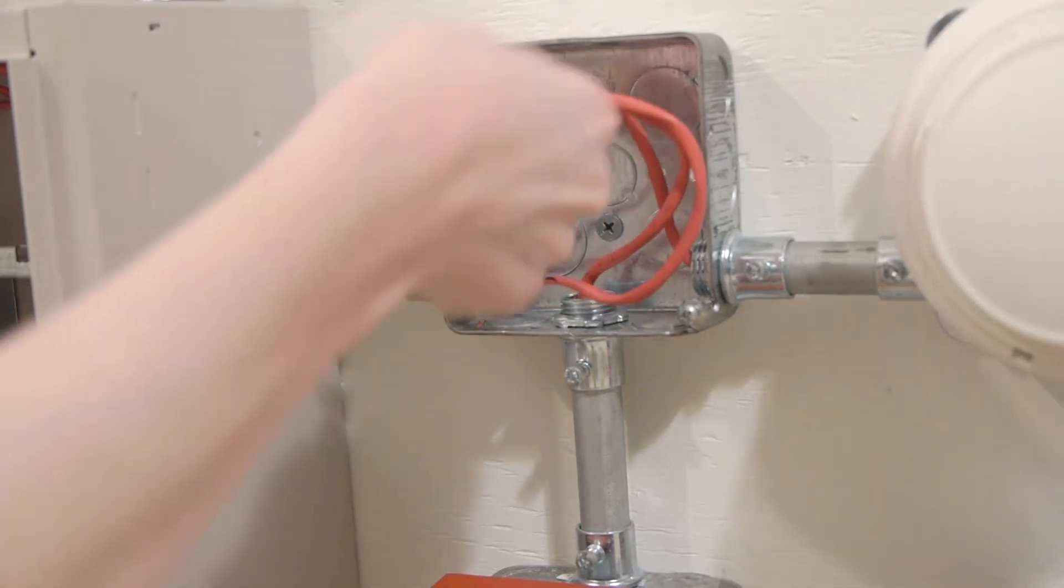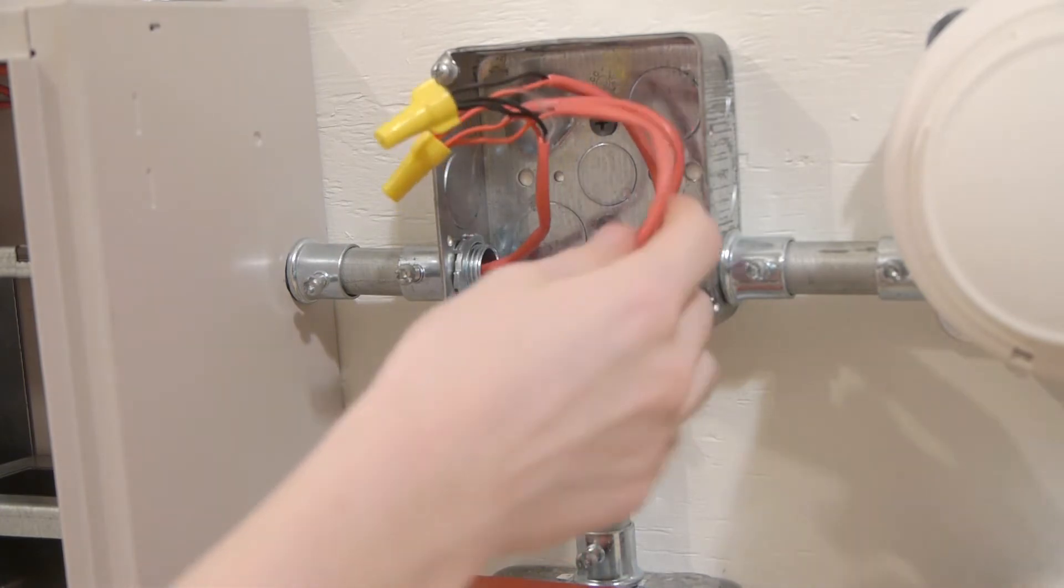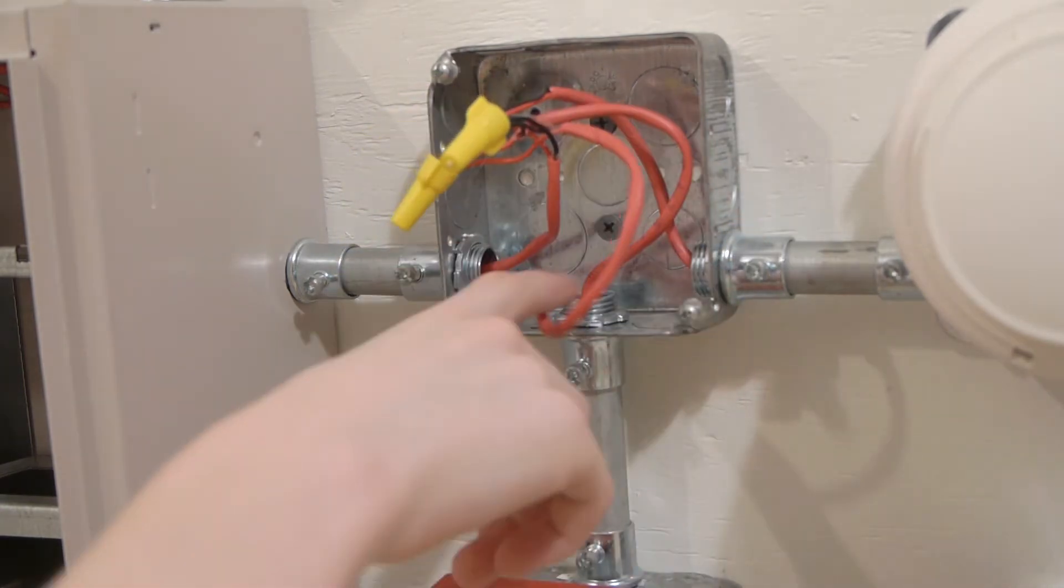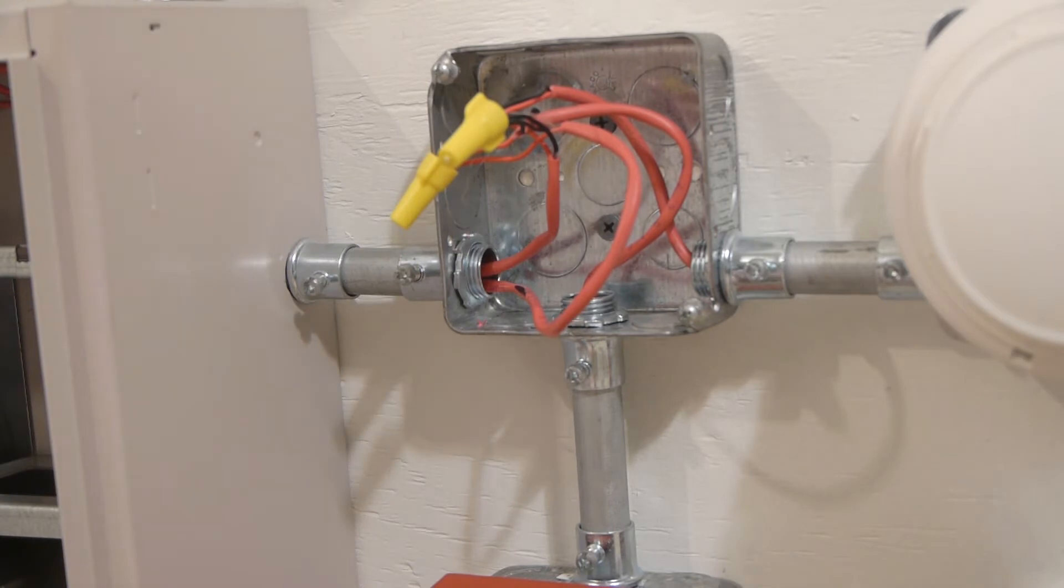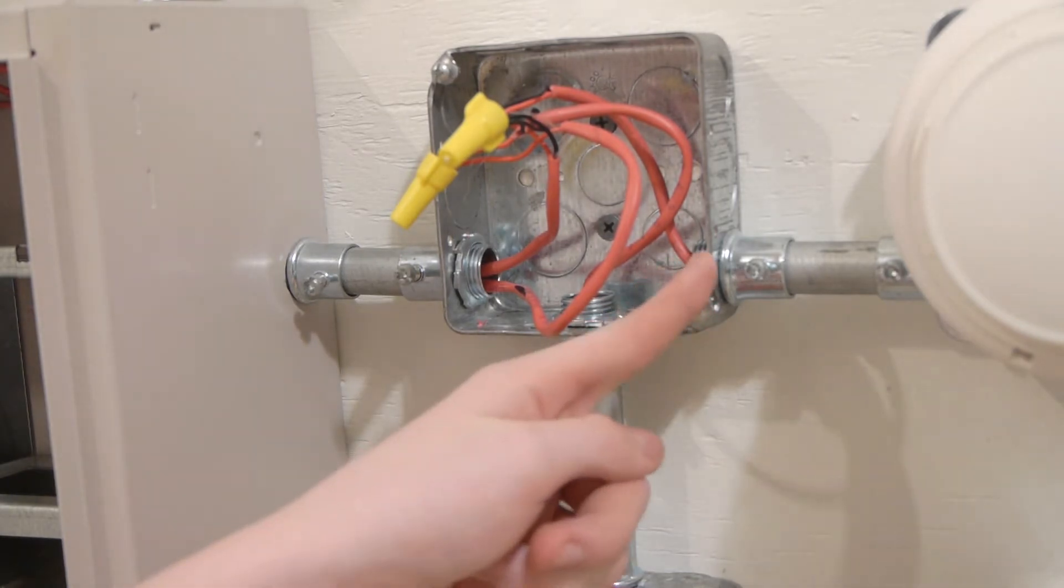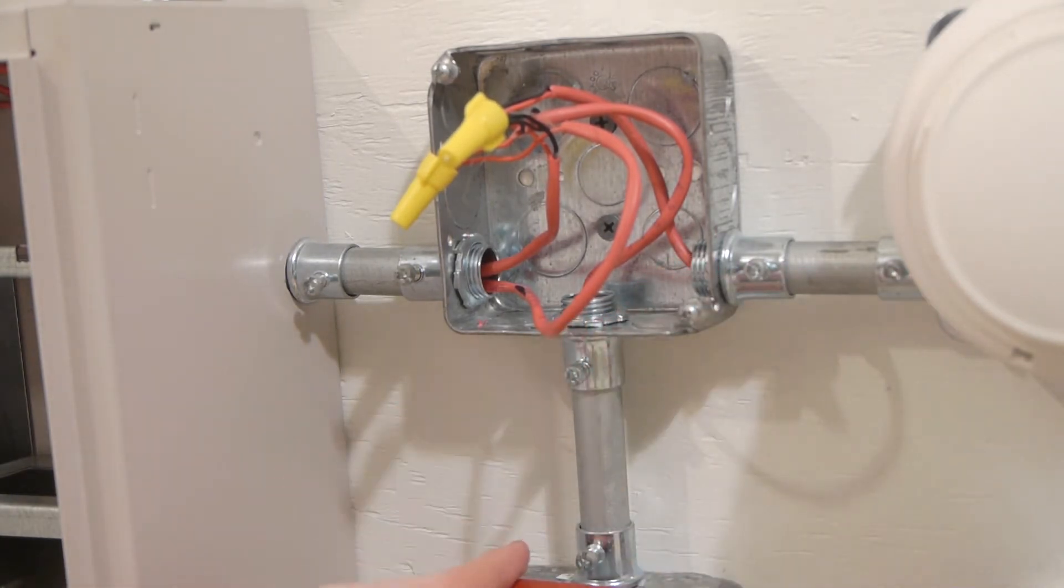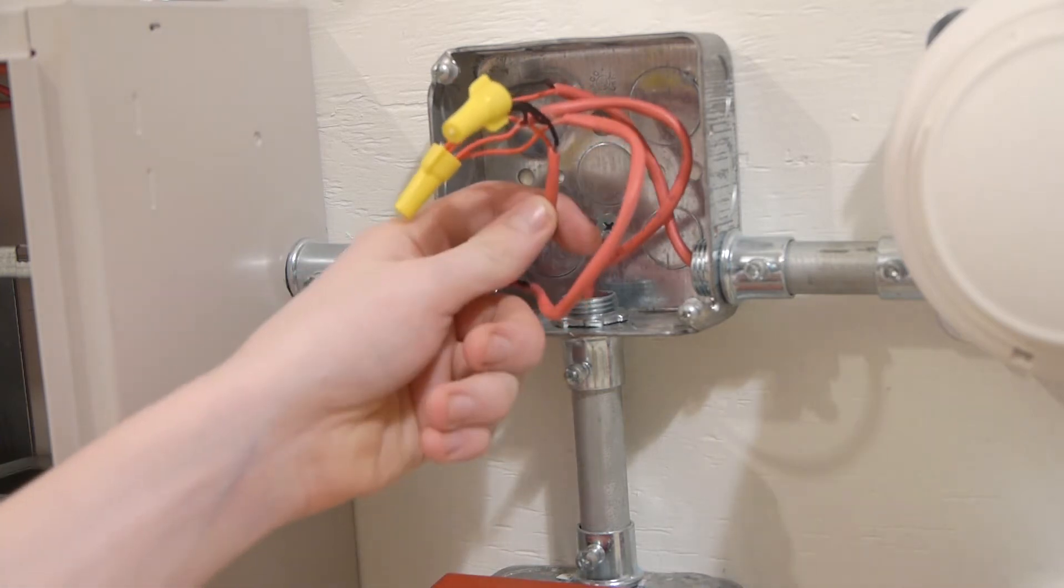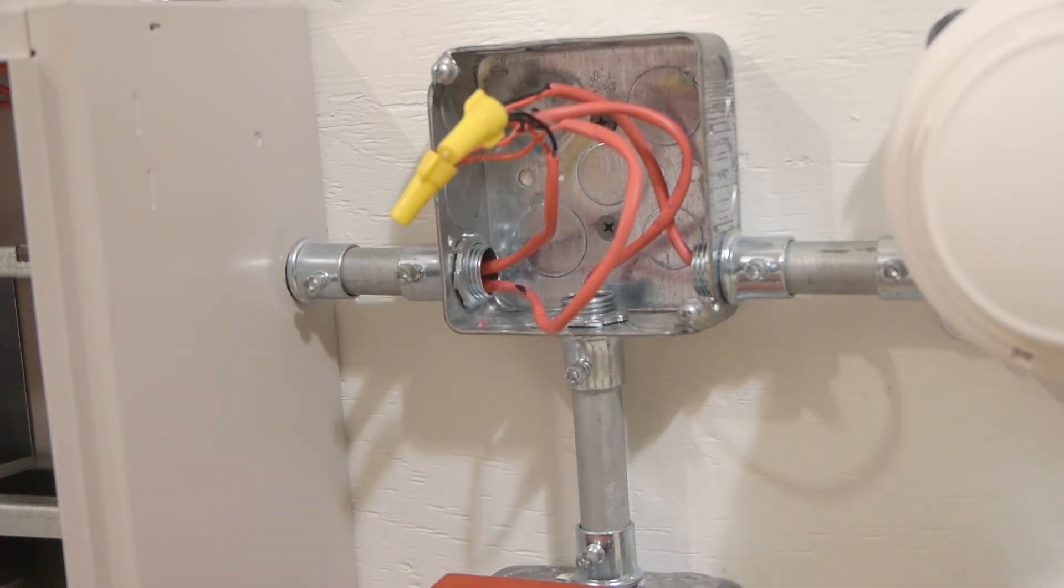Now this wire right here with the black mark on it is coming from the SLC terminals on the panel, and all the rest of the wires are going to branches of the SLC on the system. One of them goes over to these two devices, one of them goes down to the other three, and one of them goes back to the other side of the board that has a couple devices on it.